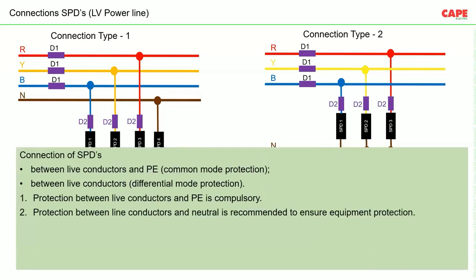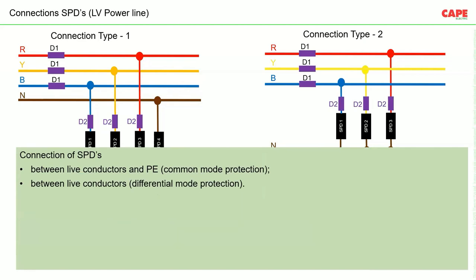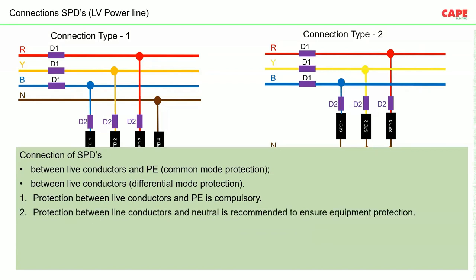Here are some key points regarding SPD connections. Point 1: connection between live conductors and PE is common mode protection, shown in connection type 1. Point 2: connection between live conductors is differential mode protection, shown in connection type 2. Protection between line conductors and PE is compulsory, whether achieved directly by connecting to the PE conductor or through neutral. Protection between line conductors and neutral is recommended to ensure equipment protection.